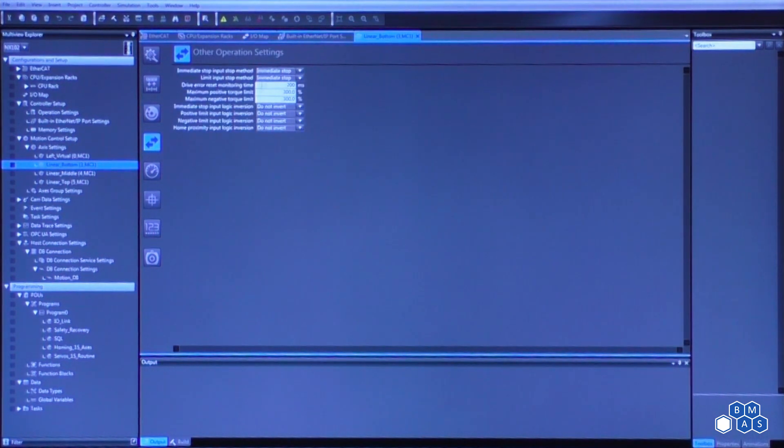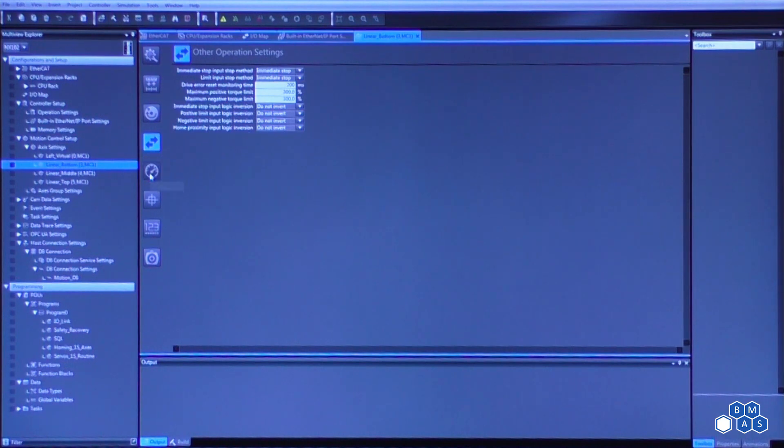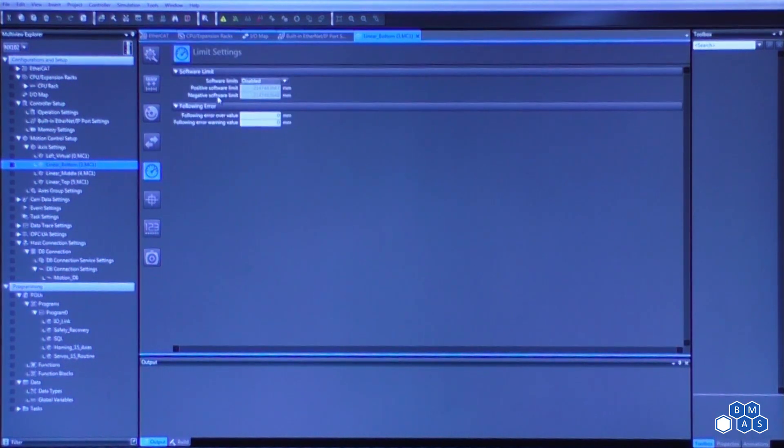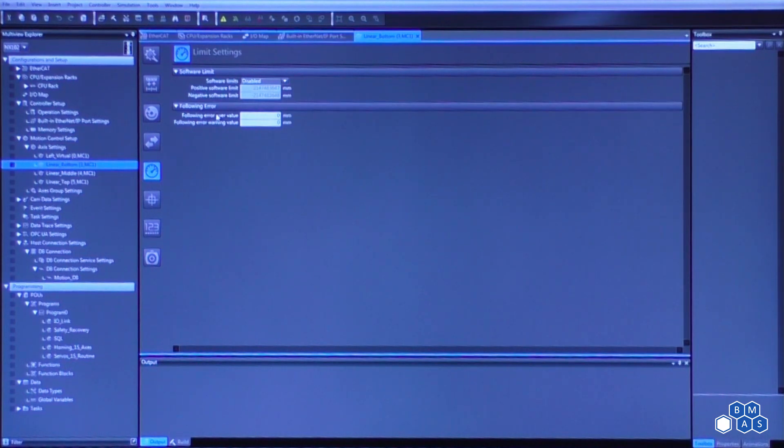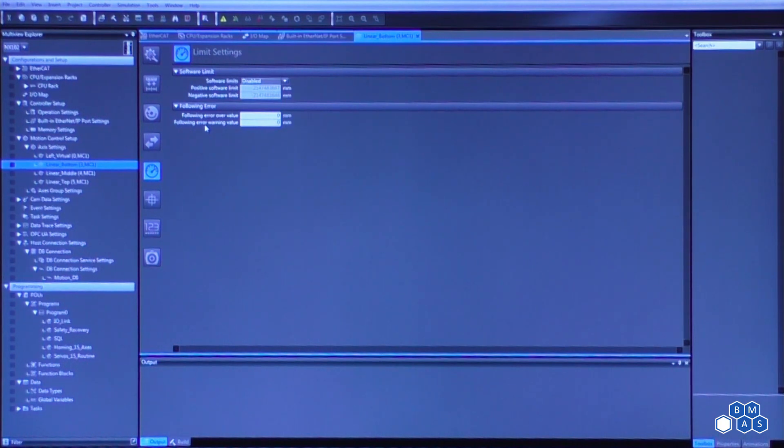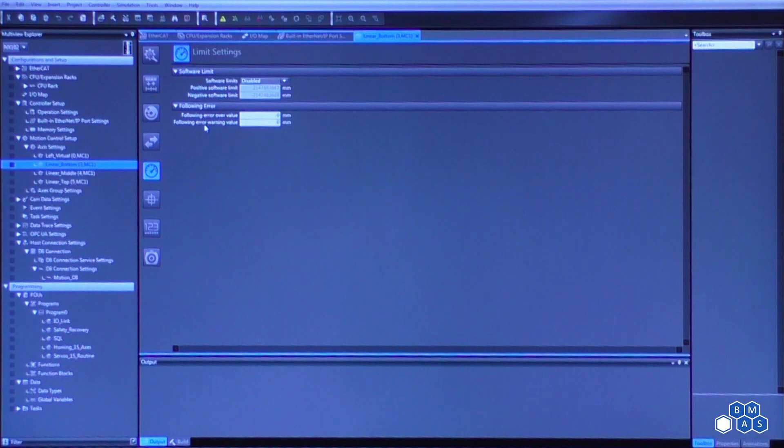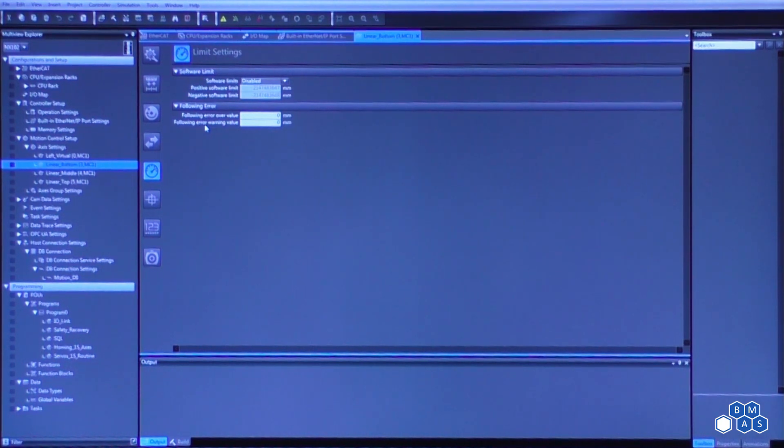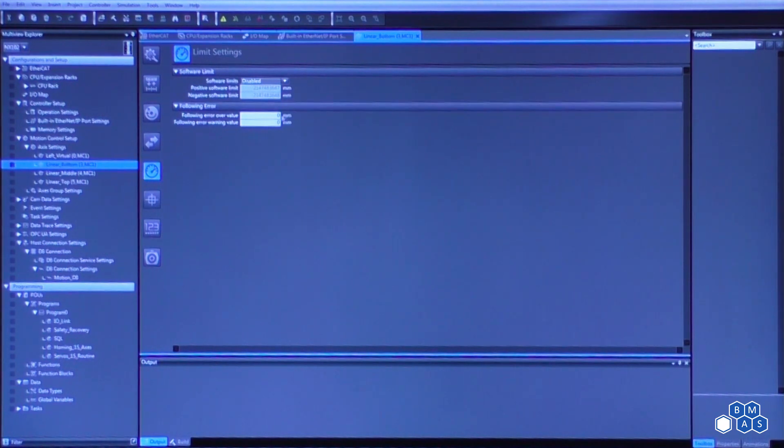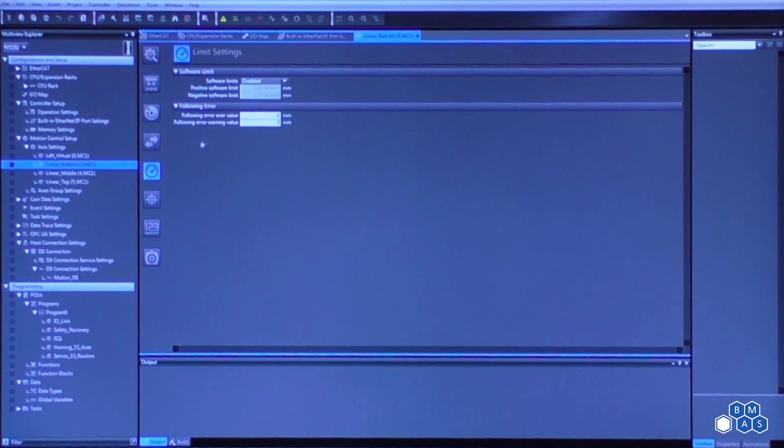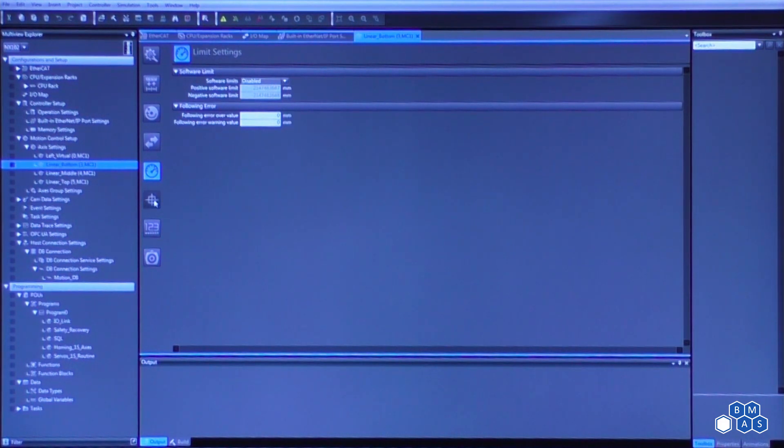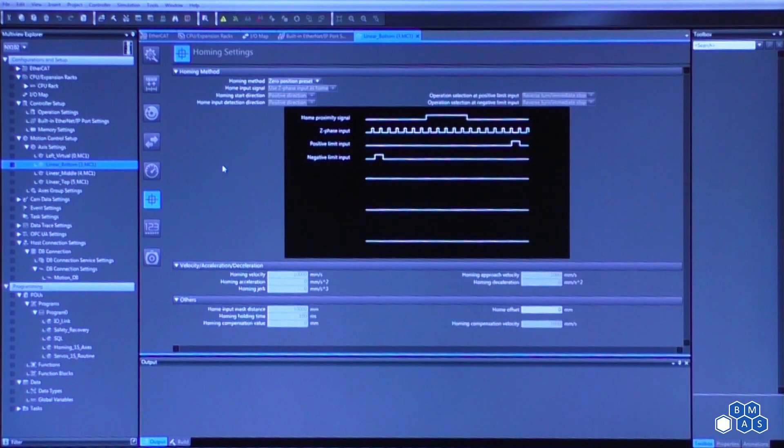So some of the other settings—if we need to change the default torque settings, if we want to apply software limits for linear motion, we can do software limits. Following error, this is if we want to apply a following error. So what this means is if you have a trapezoidal move profile and you apply your actual motion profile over top of it, if the difference between the actual and the theoretically perfect are exceeding the value that's applied here, you'll end up with an error or a warning.